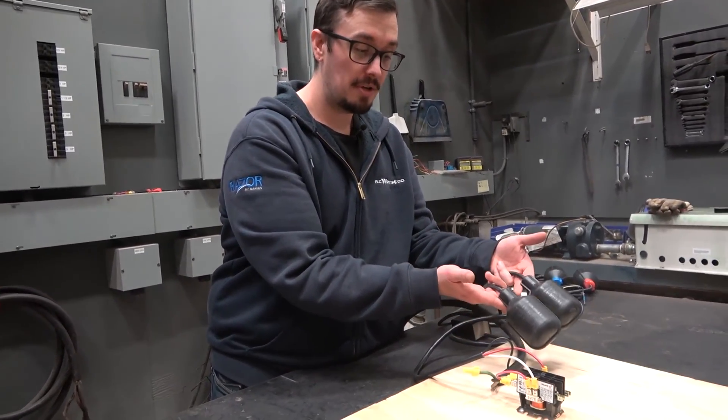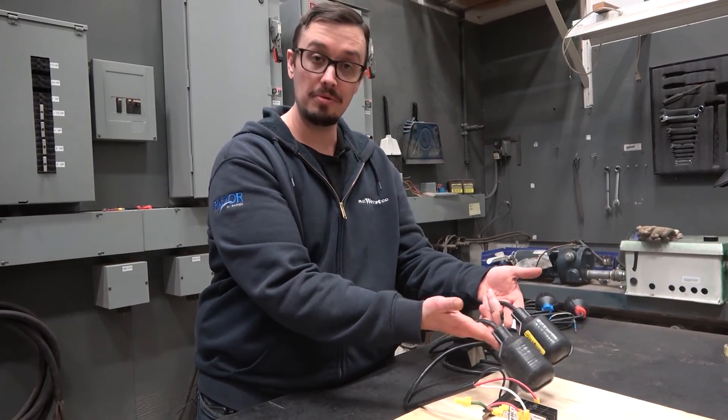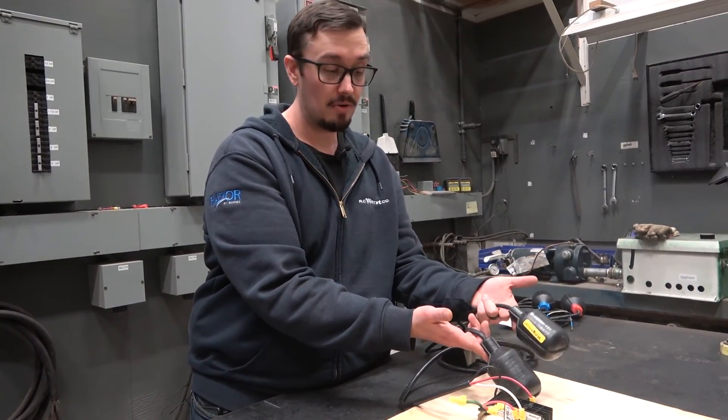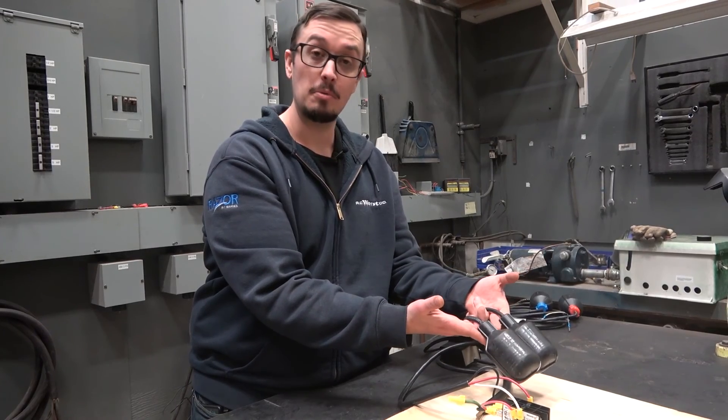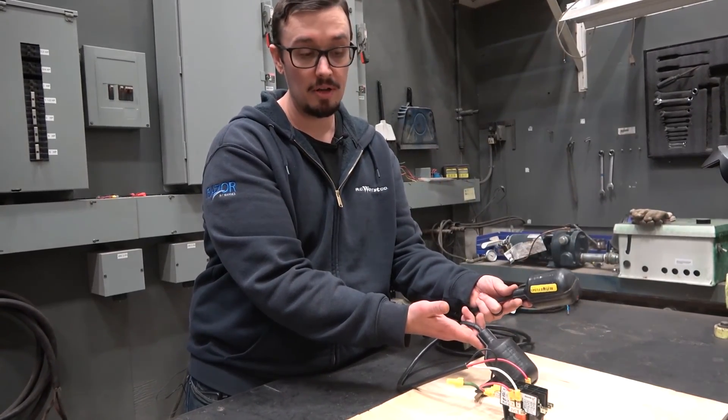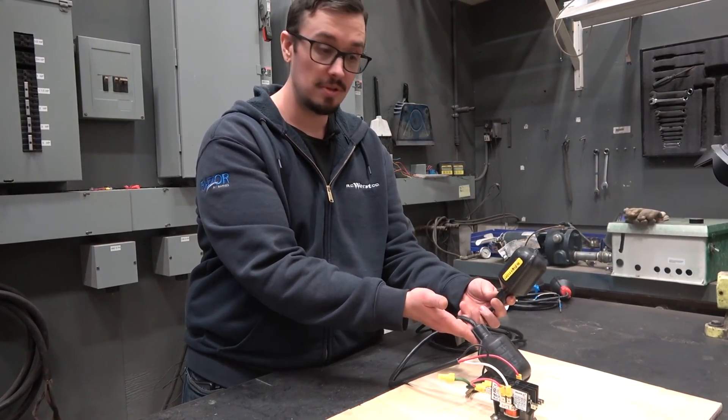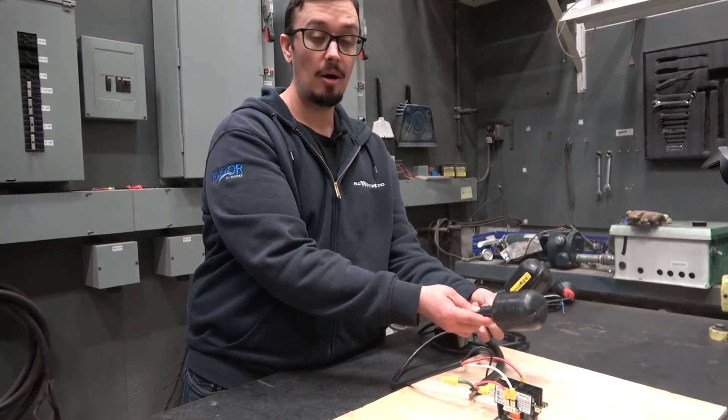We've got our two float switches here - this one being the bottom float, this one being the upper float. In a double float configuration, in a pump down application, when the water level goes up our contactor remains in the same open position, and then finally our upper float goes up, pulling in that contactor.